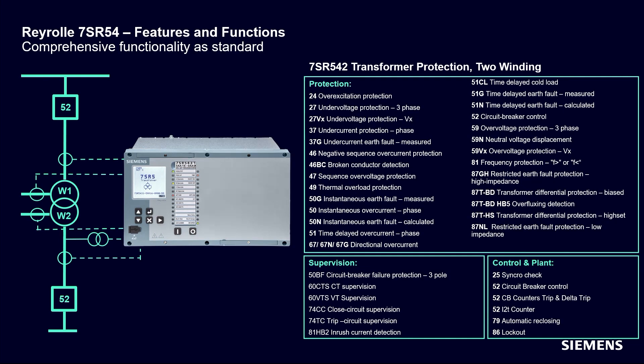The device instrumentation and metering provides real-time measured quantities and data, displayed on the relay fascia LCD or via the data communications interface. Over-excitation protection 24 detects excess core flux density that could cause overheating. Under-frequency protection on the substation transformer incomer can be used to initiate load shedding of the connected bus bar loads.